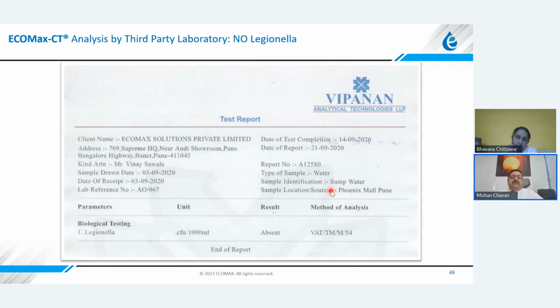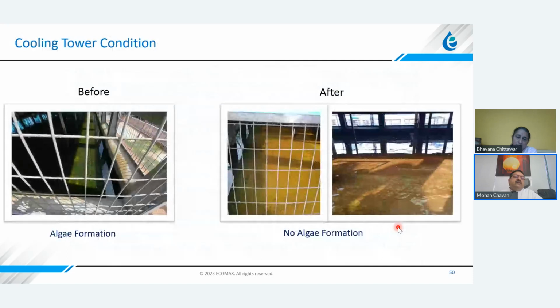Another important parameter is Legionella. When we talk about cooling towers, people are concerned about Legionella. And with electrolysis technology, Legionella cannot exist. So we have done the test for that as well. Another important slide is for algae formation. You can see here, algae formation is reduced drastically from the before case to the after case.